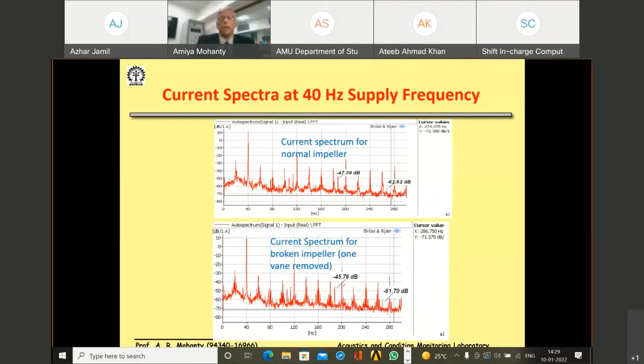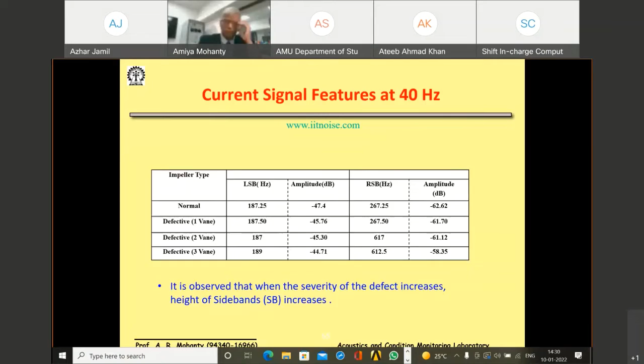And this is a current transformer. Measure the current spectrum. We could come up to the 40 Hertz supply frequency. Normal impeller, broken impeller, there is a difference. Okay, and if computer algorithms are there to notice this difference in the severity of the amplitude, it is observed that as the severity of the defect increases, the heights of the sidebands increase. So from -62 to -58. So if your measurements are good and your resolution is fine enough, you can detect faults in machines through motor current signature analysis. Okay, this was another experiment which we did.